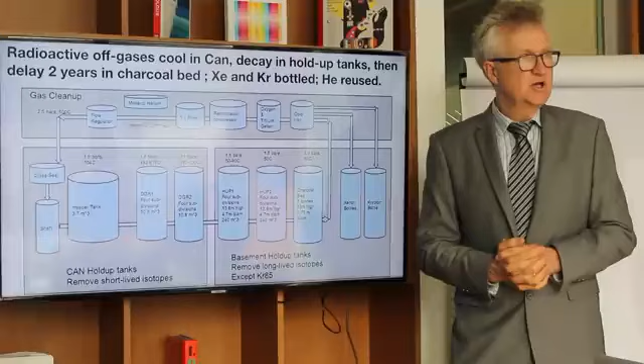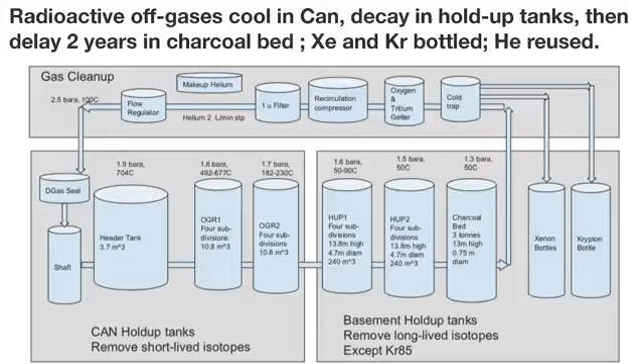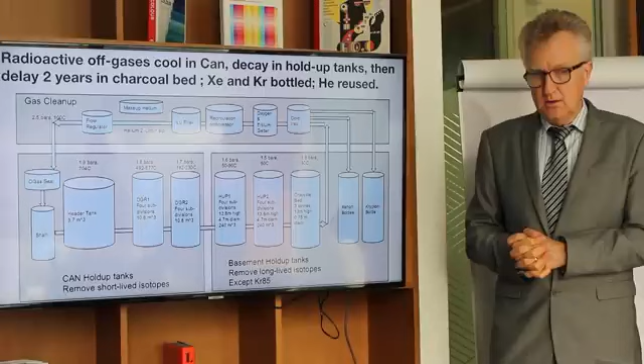It goes over into these 2 very large tanks, so that's almost 500 cubic meters worth, where the longer-lived fission products will decay away. By the time we get to here, we'll be down to just the tritium and the krypton 85. That will go over to a cold trap, which will separate out the xenon, which at this point is no longer radioactive. Put that into bottles, and it will also separate out the krypton and put that into a bottle. And then there's a getter to gather any oxygen or tritium that have leaked into the system.